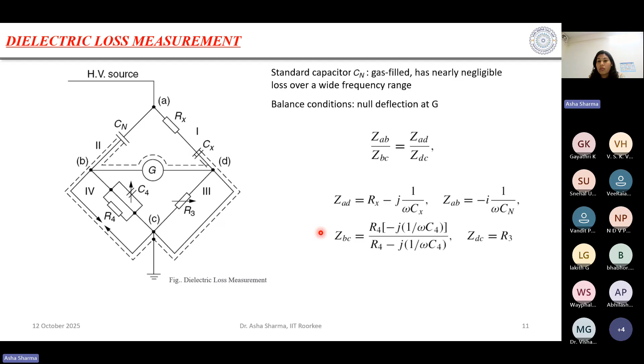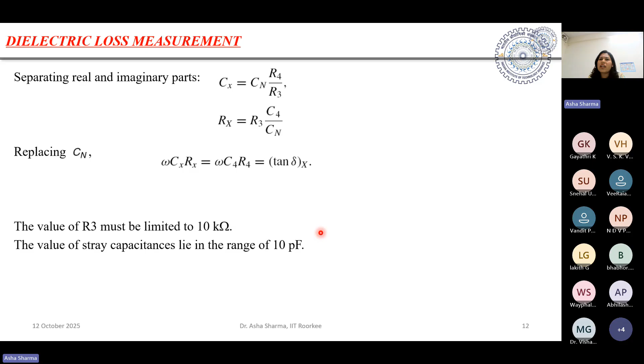So obviously, if parasitic capacitances are present between the earth and any metal point in the connection of this Schering bridge, it will affect the accuracy of the Schering bridge. So those must be avoided. And how do we take care of that? It's a different thing. We use electromagnetic shielding and other things. So that's a different story.